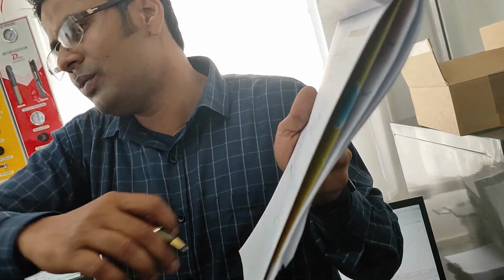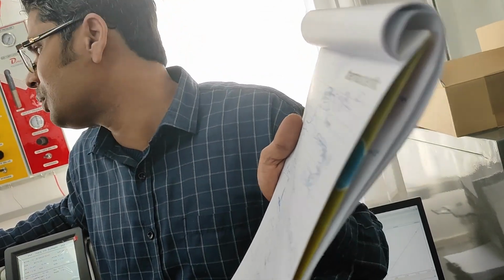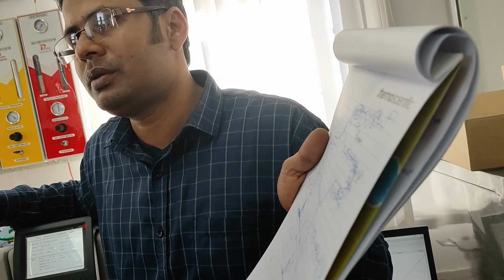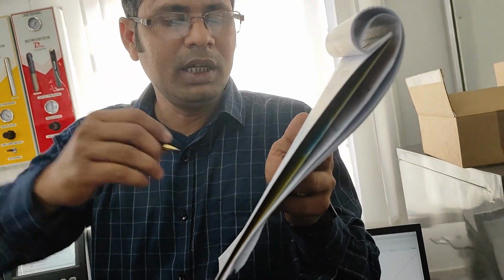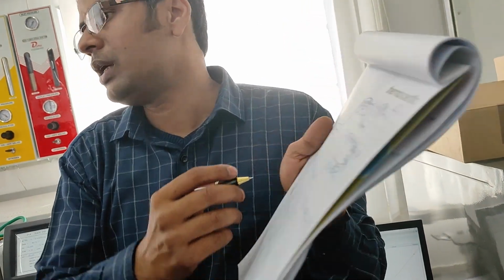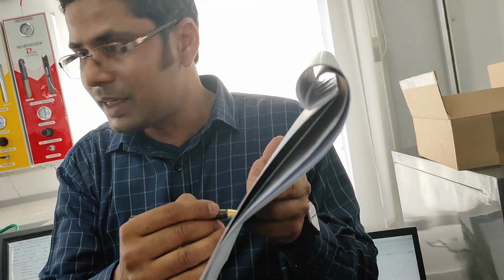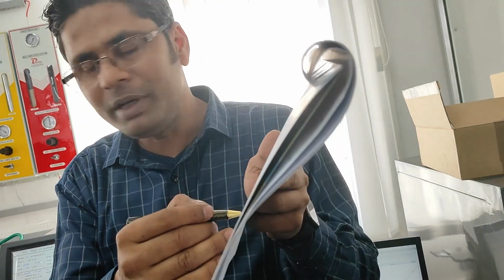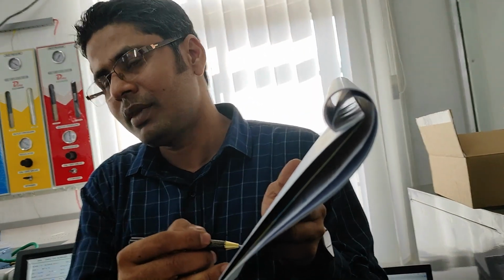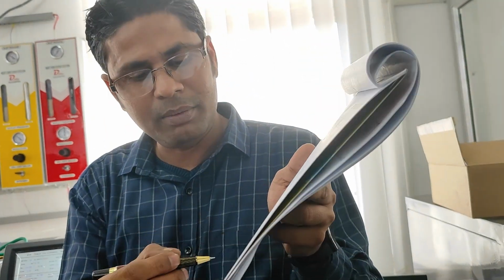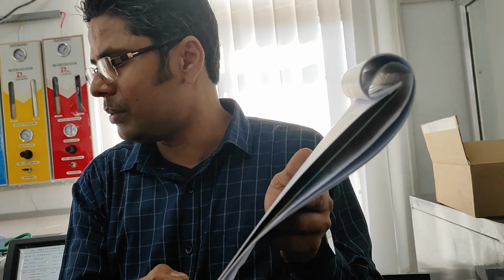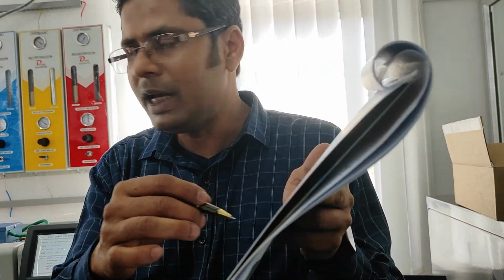If you are getting two peaks and both are not saturated, what to do? Which one to report? Only one peak is to be reported. FID? Still, I will go with TCD, because we have calibrated TCD at percentage level. Because here it is coming, that means it is percentage level, so we have calibrated this at percentage level. This one is calibrated at ppm level. So it will tally better. Okay.